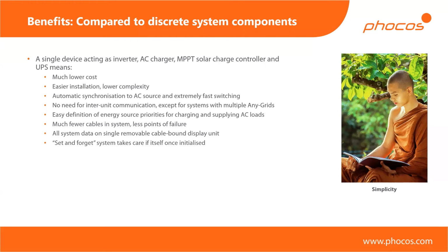Also, we have a much, much easier installation and a lower complexity, because obviously if you have many different devices that need to speak to each other, it can get quite involved to set that up and to have things running reliably for years. Then we have the automatic synchronization to the AC source. So regardless of whether you're actually using an AC source or not, as soon as you connect something to the AC input of the AnyGrid, it will automatically synchronize. It will see that there's an AC source there, there's a voltage there, it will check if the voltage is correct, it will check the frequency, and then it will adapt its own frequency to the frequency of that AC source if it's within the permissible window. So it really takes all of the guesswork out of synchronizing to AC sources, and it just means you don't need to have external synchronizing switches and things like that.